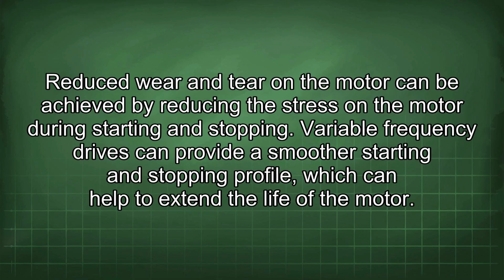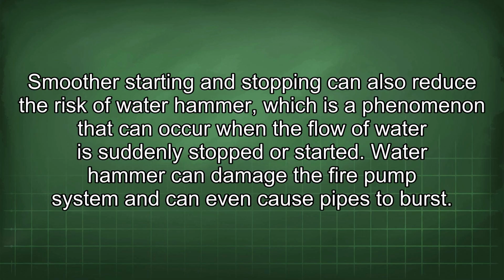Reduced wear and tear on the motor can be achieved by reducing the stress on the motor during starting and stopping. Variable frequency drives can provide a smoother starting and stopping profile, which can help to extend the life of the motor. Smoother starting and stopping can also reduce the risk of water hammer, which is a phenomenon that can occur when the flow of water is suddenly stopped or started. Water hammer can damage the fire pump system and can even cause pipes to burst.